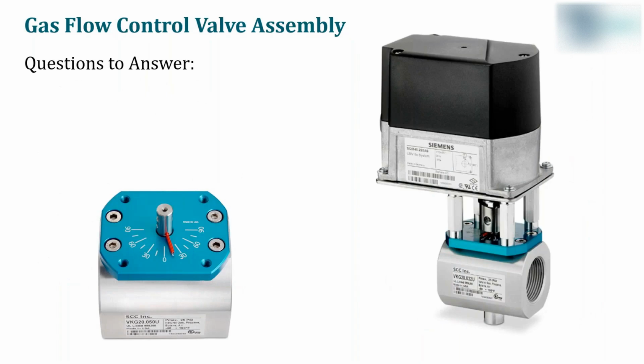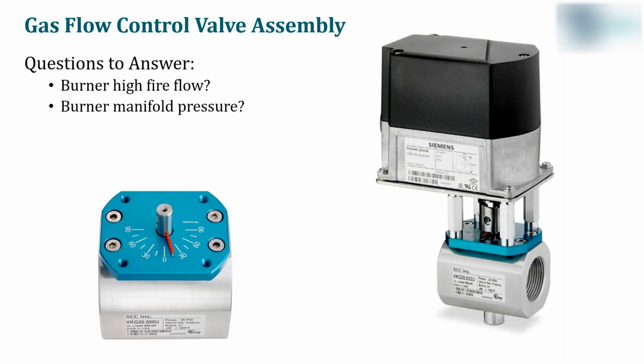Now, we move on to the gas flow control valve assembly. Questions that need to be answered: What is the burner high fire flow? What is the burner manifold pressure? What is the pipe size? And is it an indoor or outdoor application?